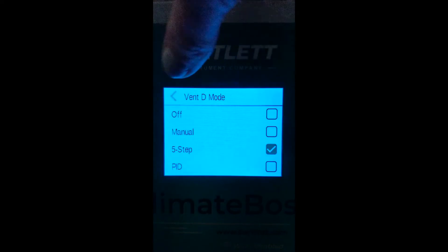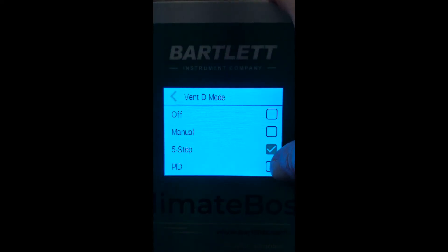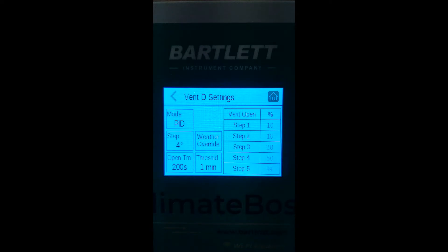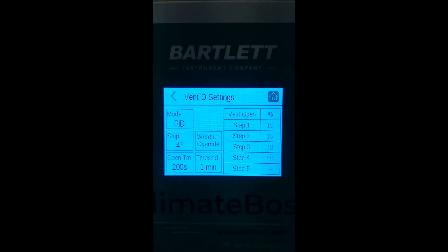Let's discuss the difference between five step and PID. PID mode stands for proportional, integral, and derivative, which is a mathematical way of determining how far to open a vent. In this mode, calculations are performed every minute. The current percentage open will be modified according to three conditions: if the temperature is rising or falling, if the temperature is above or below the vent set point, and according to how long the temperature has been at its current reading. To prevent unnecessary movement, the controller will only move the vent when the accumulated change will result in at least seven seconds of motor runtime.